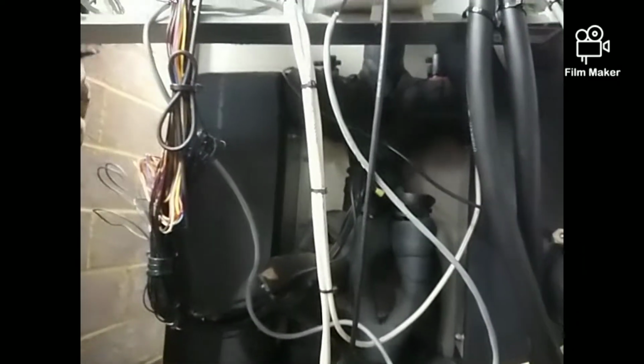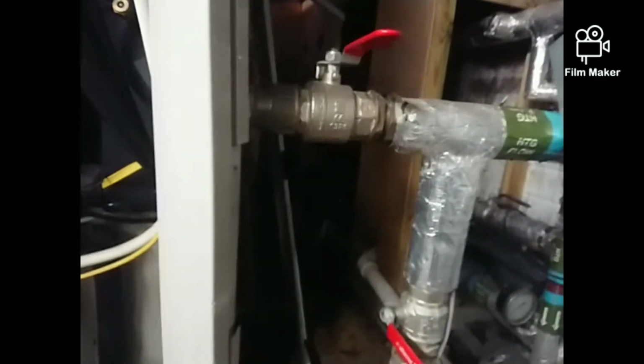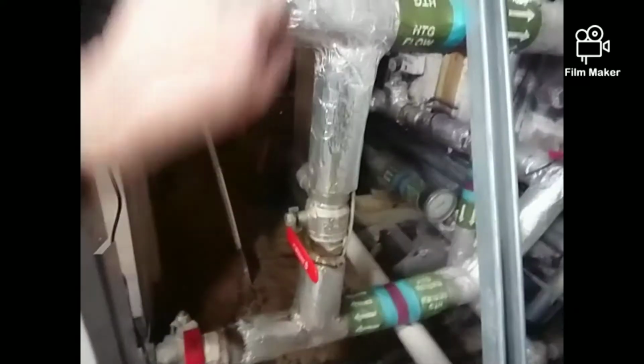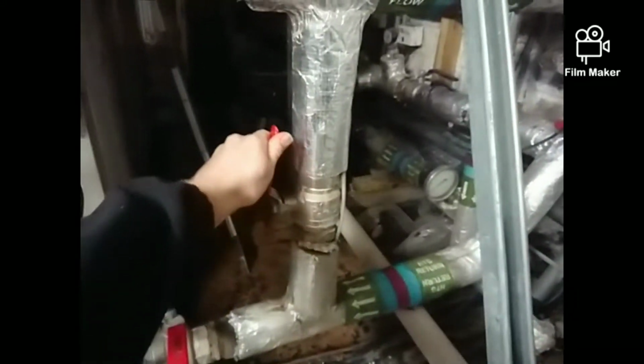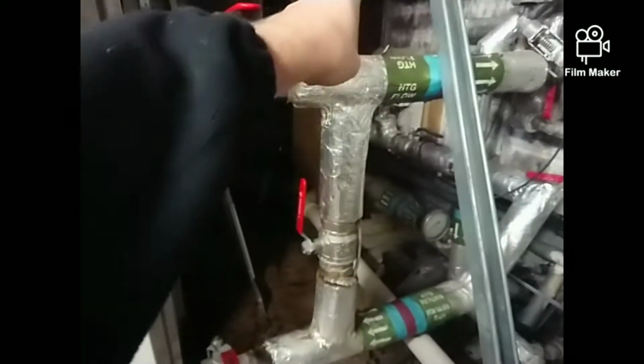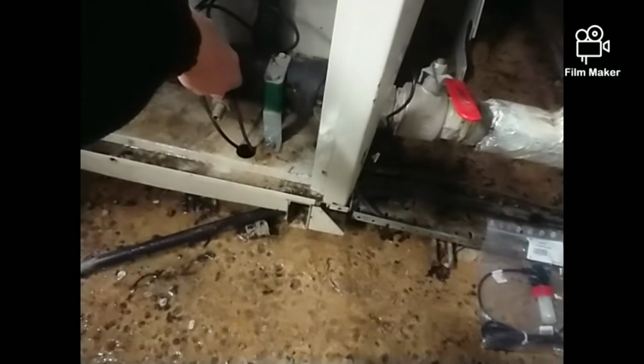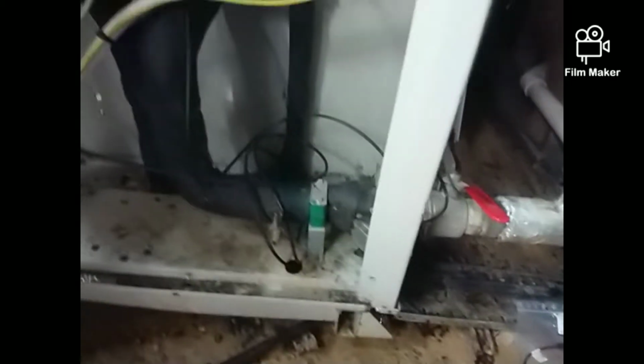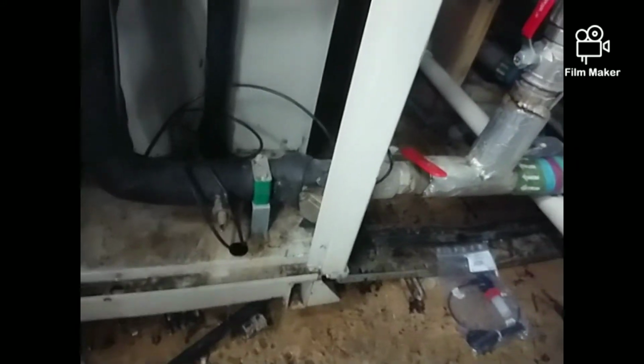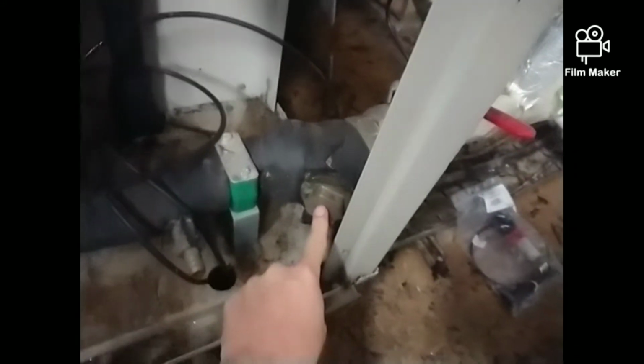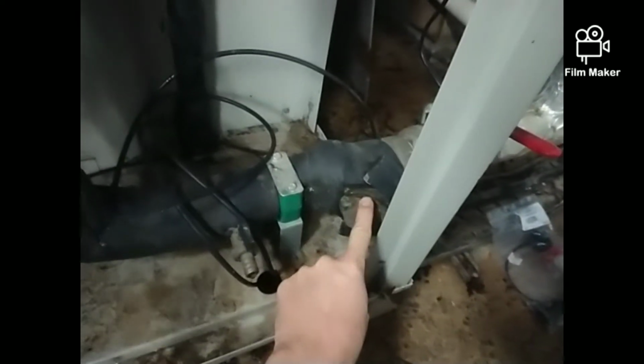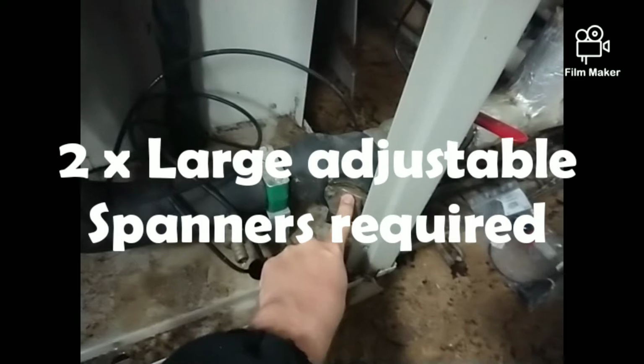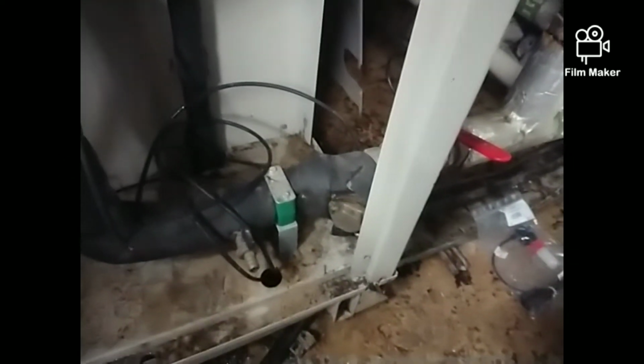Now, to replace it, you need to drain down the heat exchanger side by simply isolating the flow and the return. And because it's flow and return, you need to open the bypass valve, which allows the water to miss our coil and go through the bypass back to the pump. So we've now got isolation here and here. We've got a drain port here, which you can let the water out like that. Water will come out of that eventually. And also, while we're draining the system down, we're going to remove the inline filter, take that out and clean it. It's a job you may as well do while the system's dry, and it doesn't take more than 5 minutes to do it. And that's pretty much it.